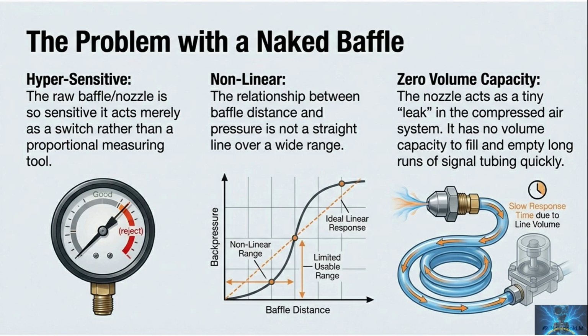The problem with a naked baffle. A raw baffle and nozzle is too sensitive, so it behaves more like a switch than a smooth measuring device. The pressure versus distance relationship is also non-linear over a wide range, so it is only nice and linear in a small usable region. The nozzle acts like a tiny leak with almost no volume capacity, so long signal tubing fills and empties slowly. That tubing volume creates slow response time and mushy control. So the baffle and nozzle is an amazing sensor, but it needs help to become a stable instrument.